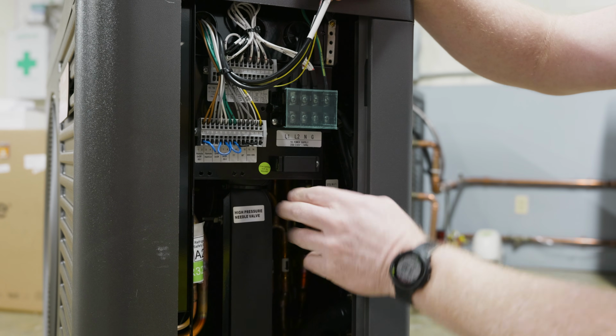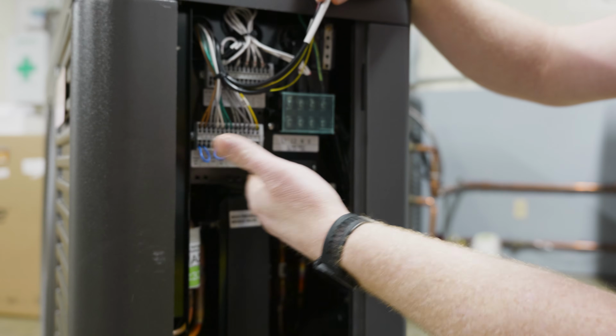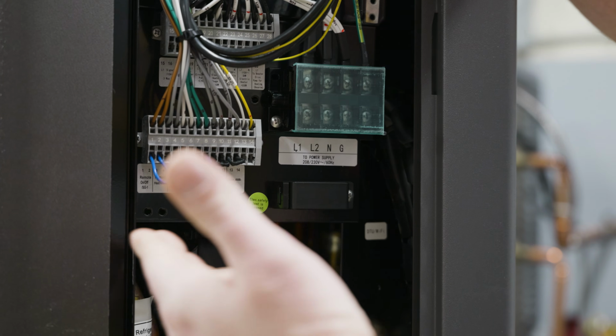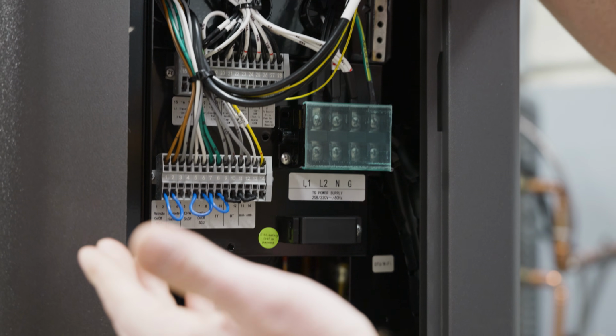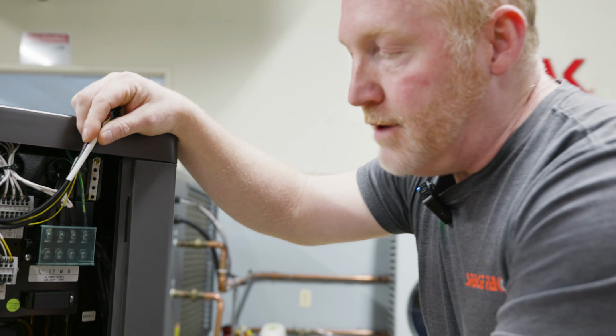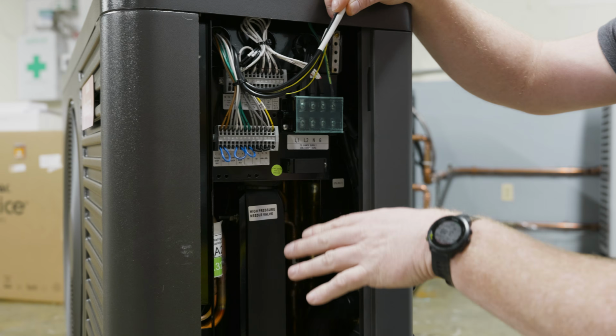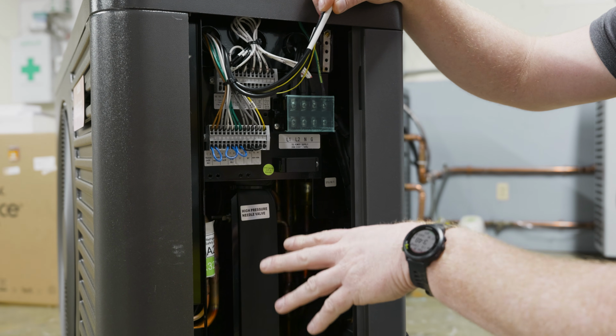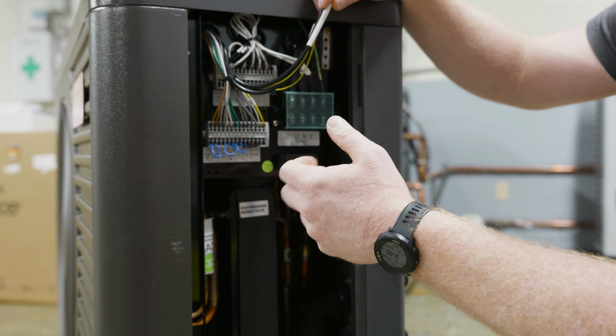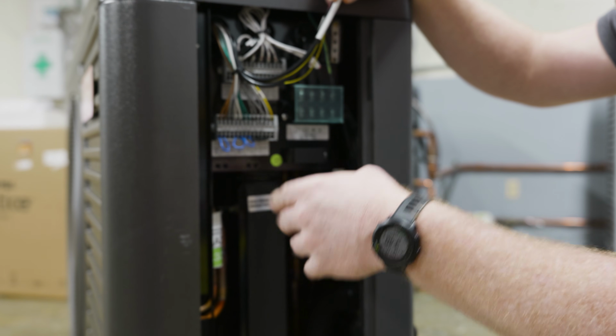Now, our low or no voltage connections here. These are what we're going to use to turn the unit on, to choose either heating and cooling mode, auxiliary inputs, outputs, and so on. Please pay special attention to the wiring diagram, as these connections, many of them are no voltage connections, and adding voltage to those connections will compromise the control board.